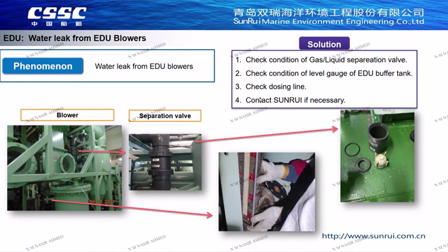The next fault is the seawater leakage from EDU blowers. As in the picture below, this failure usually occurs in the old system, which may happen in the system before 2016. New design system will not have this. This is mainly caused by gas-liquid separation valve stuck in one position. Increasing water could not be stopped by valve and overflows from blower.